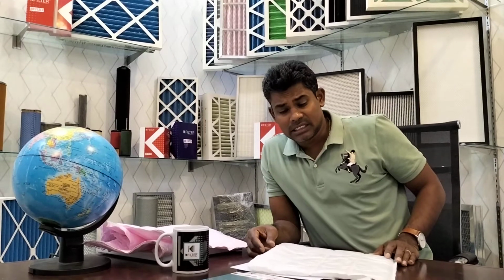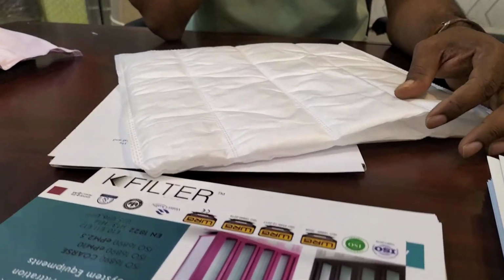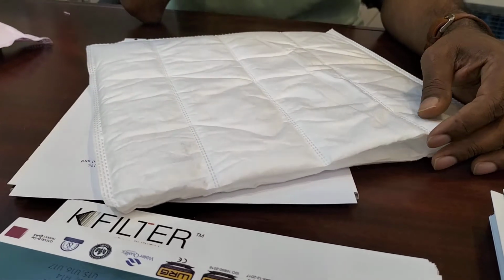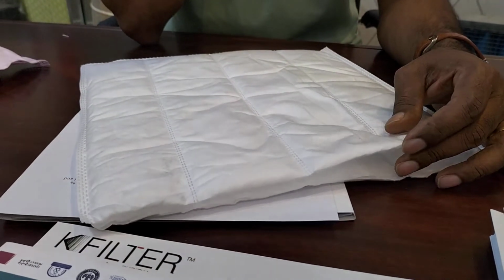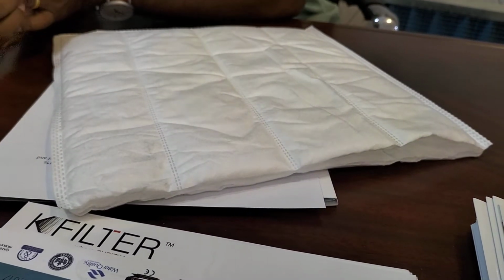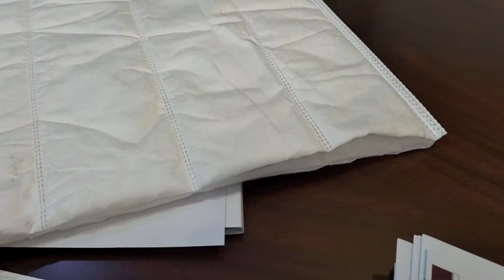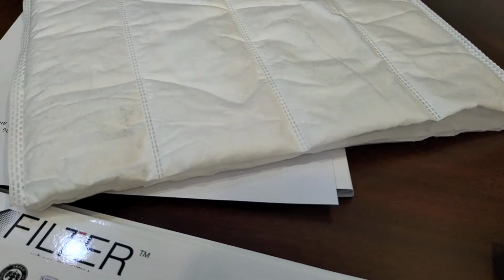And now we go to the fine dust filtration section, ISO 16890 ePM1 classification. ePM1 classification means it's called F9 filtration. F9 filtration is also available, in a white color, so you can identify it by the white color. That means F9 classification. F9 classification also covers 95 to 98% efficiency, and is normally used for clinical applications such as hospitals, clinics, airports and chemical laboratories and all.